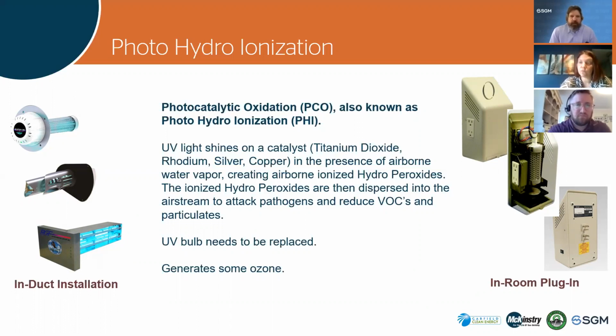It's basically UV light that shines on a catalyst like titanium dioxide, rhodium, silver, or copper, in the presence of airborne water vapor. So it creates ionized hydroperoxides. These ionized hydroperoxides are then dispersed into the airstream and attack pathogens and reduce VOCs and particulates. The UV bulb, just like any UV bulb in any system, usually needs to be replaced annually, so it can be expensive, and it does generate some ozone.